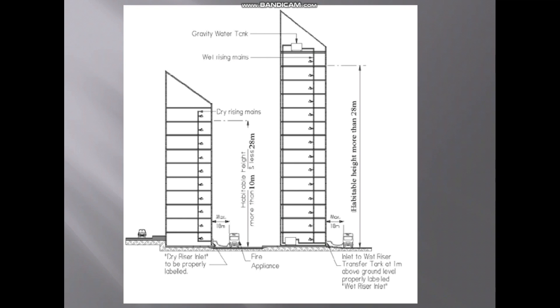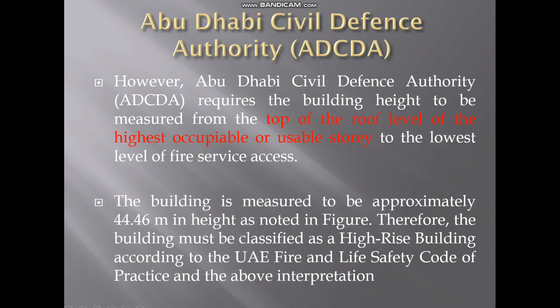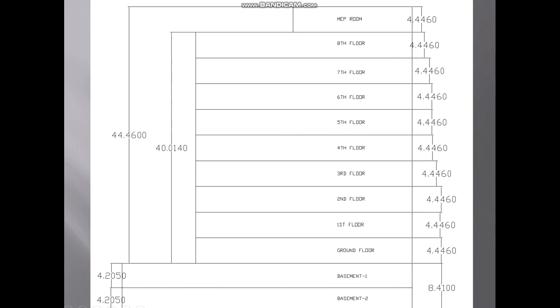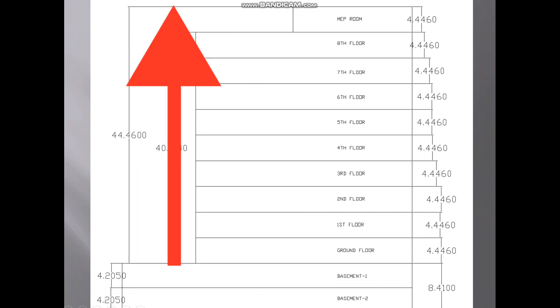But there is an exemption. For example, Abu Dhabi civil defense has a different approach. Abu Dhabi civil defense authority requires the building height to be measured from the top of the roof level of the highest occupiable or usable story to the lowest level of fire service access. So in our example, from the fire engine standing at the ground floor to the top of the roof — which is the top of the MEP room — that height is 44.46 meters. This is the habitable height as per Abu Dhabi civil defense.